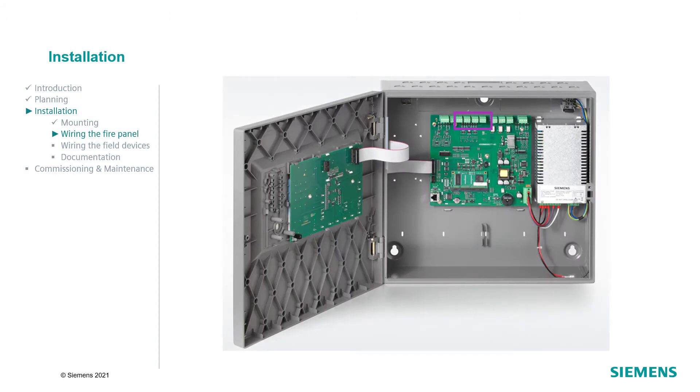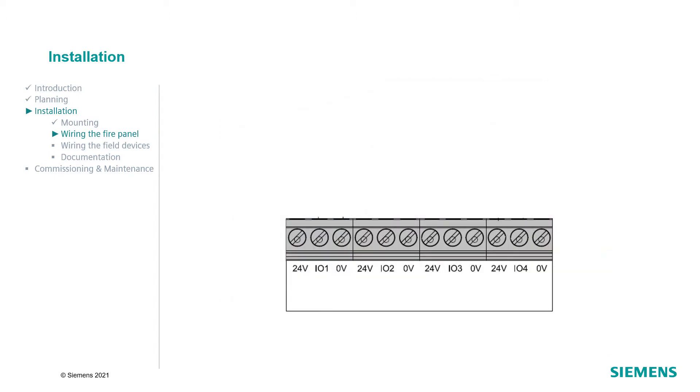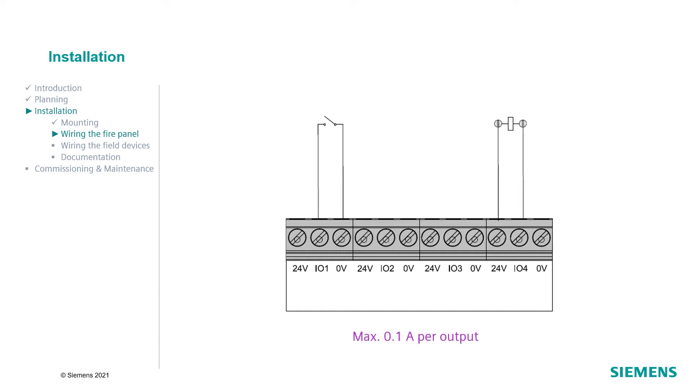The panel main board has also four configurable inputs and outputs. Each one can be configured as an input or as an output. Connect 0V and the I.O. if it shall be configured as an input. Connect 24V and the I.O. if it shall be configured as an output. If it is configured as an output, the maximum current of each output is 0.1A. The maximum current of all four outputs is 0.2A.